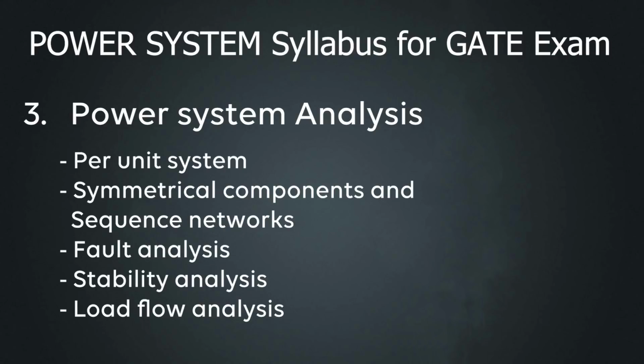When you want to solve any power system engineering problem, there are two methods: you can go with absolute analysis, or with per unit analysis. But if you do calculations with the absolute system, it is very complex, just because of transformers - the impedance referred to the primary and secondary of a transformer in the absolute system is not the same.